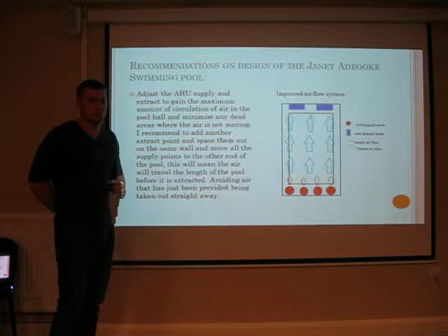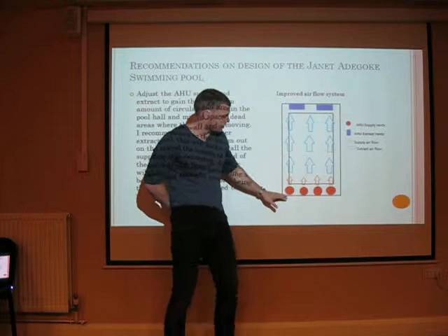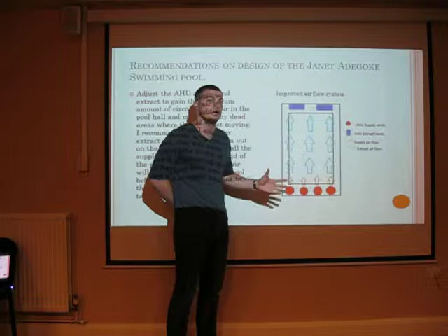I would also like to change the airflow system for the way the Janet Adegoke swimming pool is run. Instead of their normal central inlets, we could have inlets right at one end and the extractor points at the other end. This would use the air throughout its full potential before it's extracted, so you're not pumping in fresh air and having it taken away straight away after heating it, wasting money on gas. So the recommendation is to put the inlets at one end and the extraction points at the other. Thank you very much.